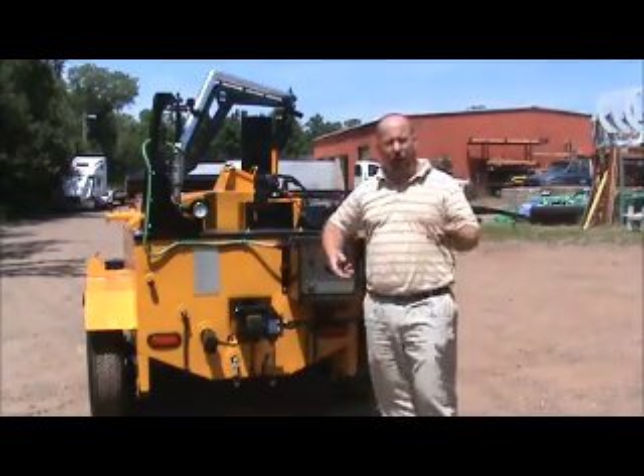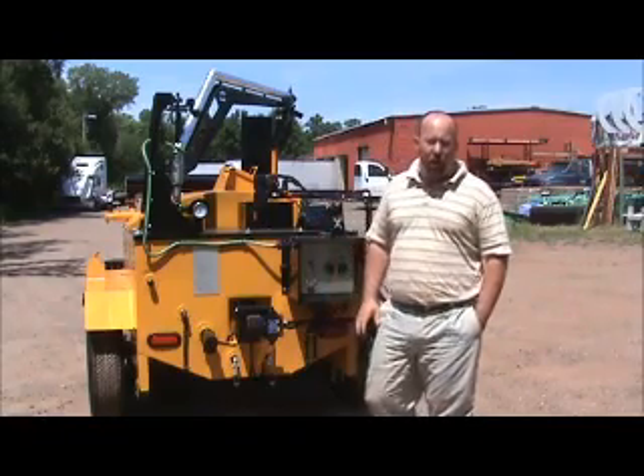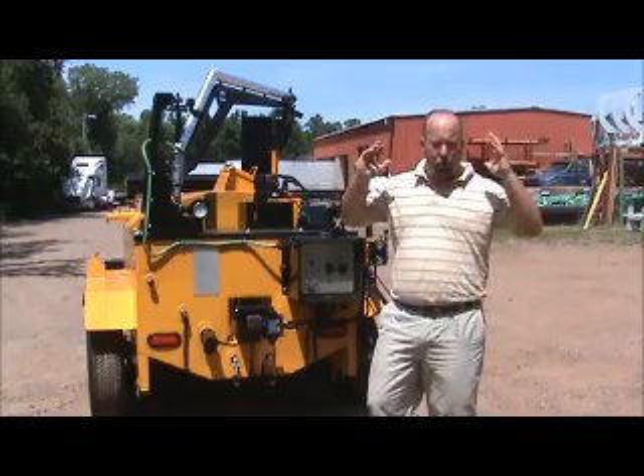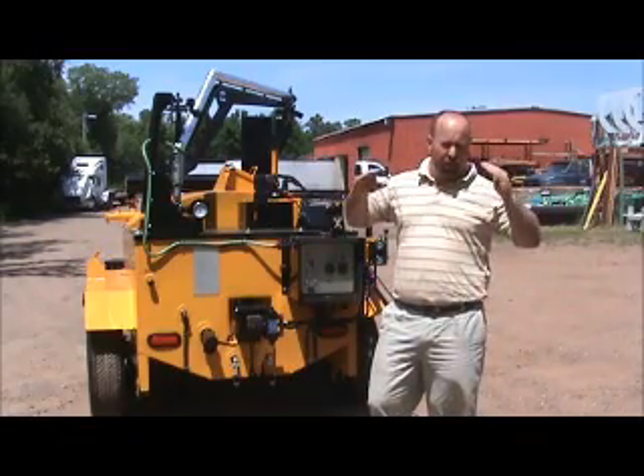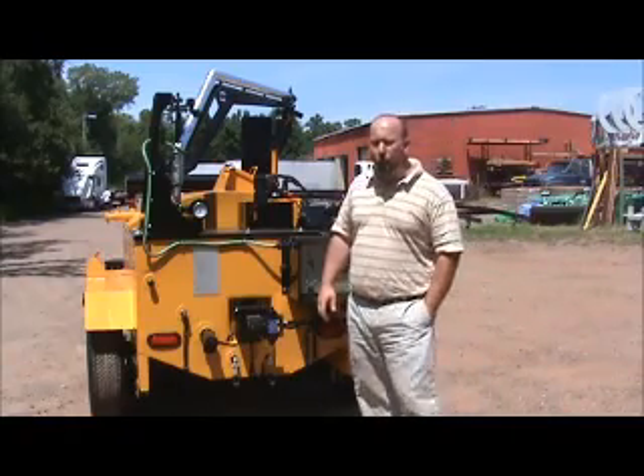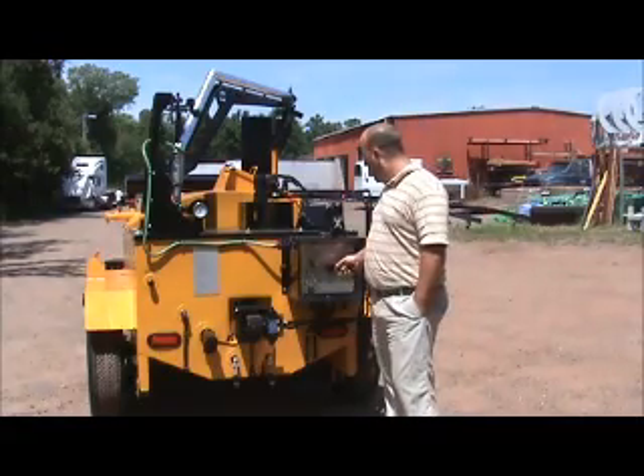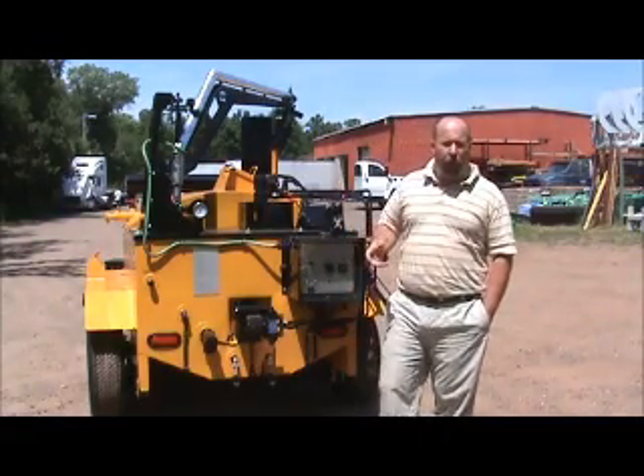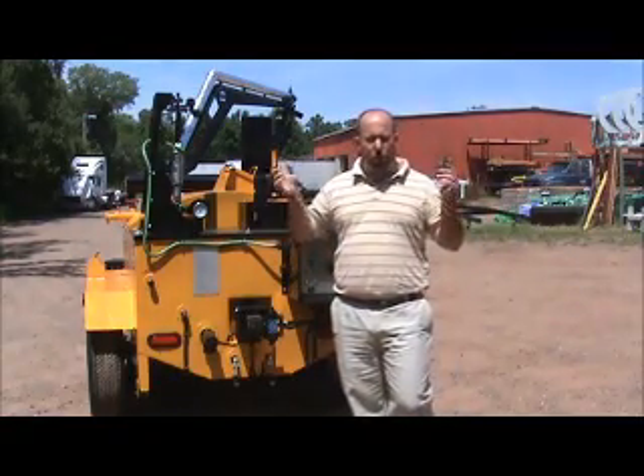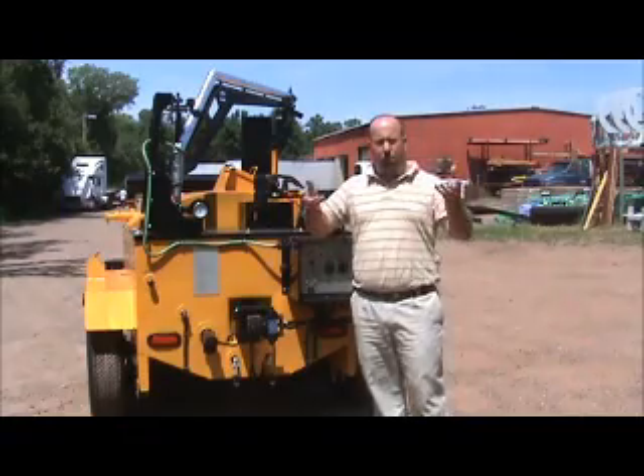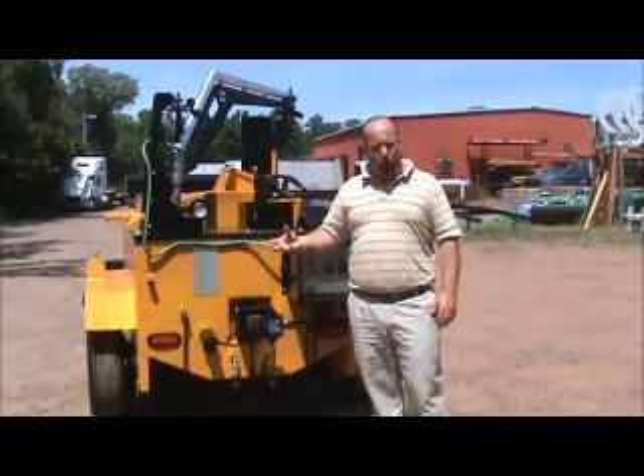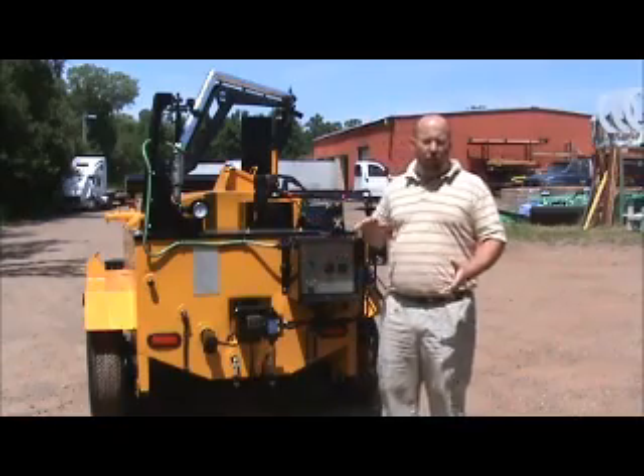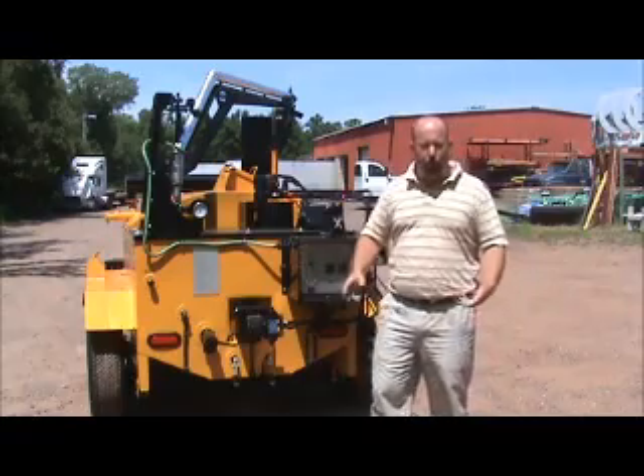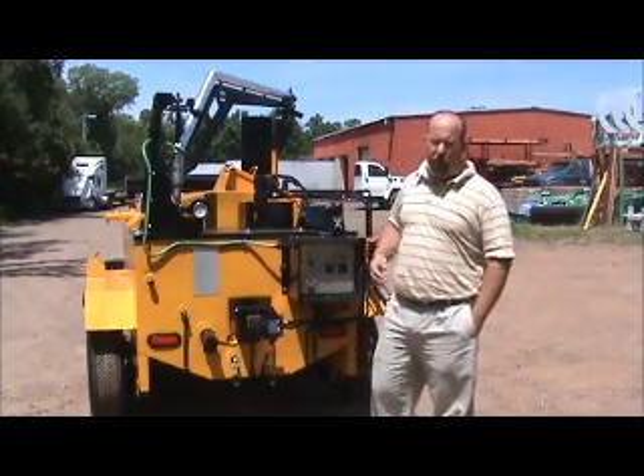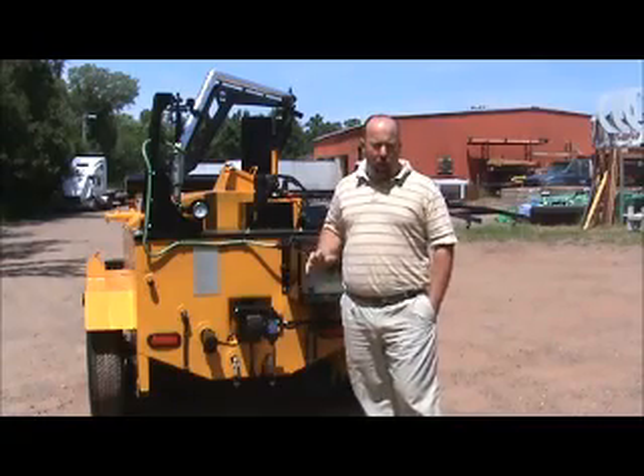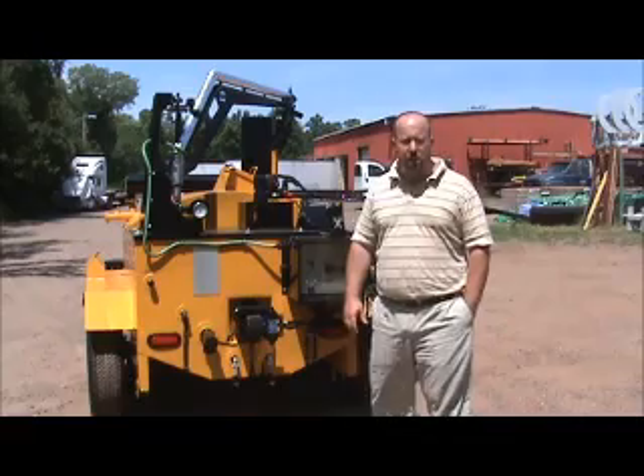Once you set the thermostats, it's just going to come on and off as needed, just like a thermostat in your house. If we set it at 400 degrees, it's going to come up to 400 degrees and shut the burner off. Once that product starts to drop, I believe it's 5 degrees, the burner kicks back on and keeps things warming up. It's not uncommon, especially in the morning, if we set our heating oil temp to 425 or 450, the burner will come on. Once the oil hits the temperature, the burner will shut off, and you'll actually see a little bit of temperature creep, just because the burner's off, we're still cycling that hot oil through the kettle. You'll see that temperature creep, and then the temperature will start to drop, and then the burner will kick back on by itself. So as long as we leave that set at 425 to 450 on the oil, and then run your product at whatever temperature the manufacturer recommends, you'll be okay.